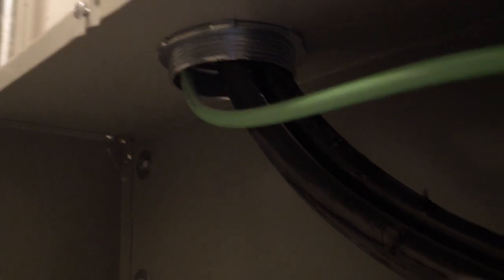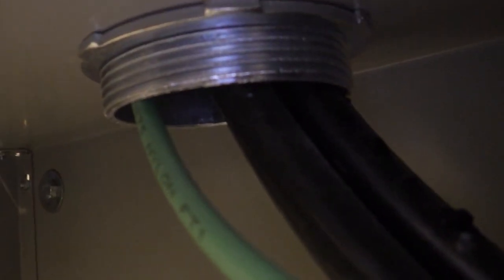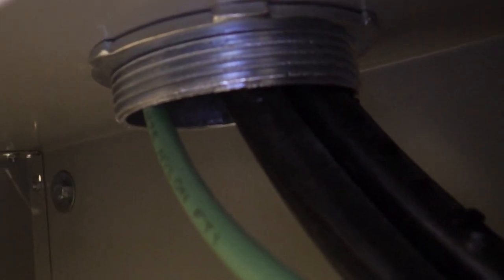There's no bushing there. And you can see the wires are all nicked up there. Look at that. Insulation is a little damaged there. That's a pretty sharp edge there, certainly not smoothly rounded.